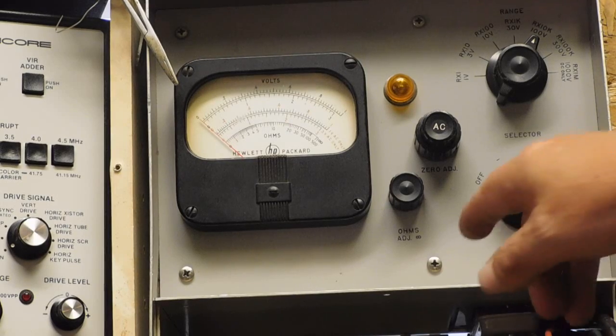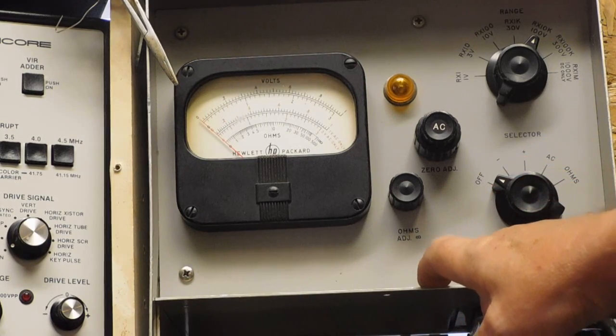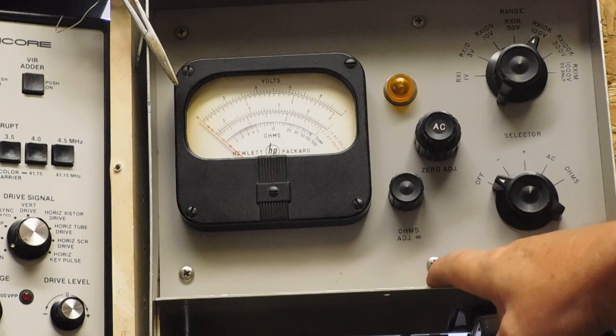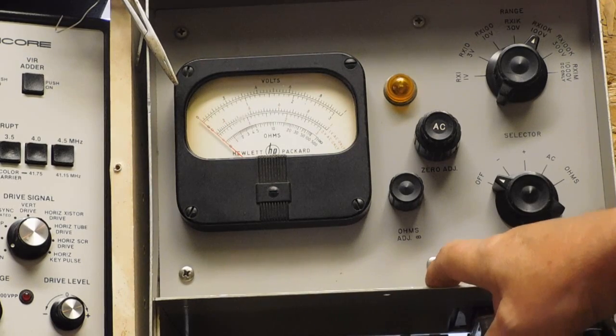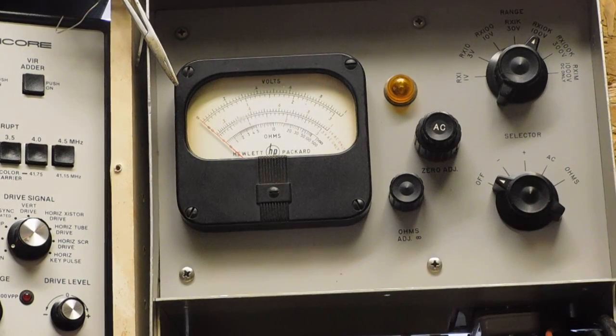Now the unique thing about it, it has no internal battery for DC or for ohms. The ohms gets its power off the filament winding on the transformer. They rectify it and supply it, so that's where it's getting its power.